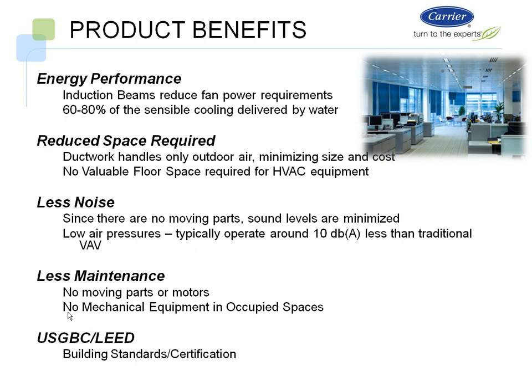Remember, these are coming out at velocities that are draped across the ceiling and coming down as they're trickling down through the space, and then the Coanda effect brings up the air through that coil. So you're not bringing up a lot of dust particles and everything else that you'd be shaking up through the room like you might be doing with a fan coil or some other type of unit that would require a little more maintenance on the cooling coils. So again, maintenance is greatly reduced. Talk about your air side, your primary air source, and the reduction there, and the reduction in the complexity of that unit as well.